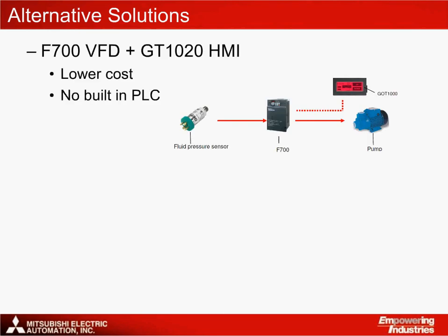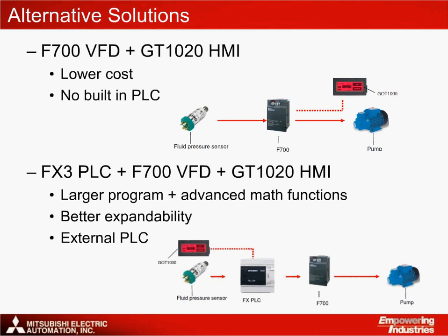As with all our applications, there are different ways to design the system solution. The F700 and GT1020 HMI offer a more affordable solution. The F700 is cheaper than the A700; however, it does not feature a built-in PLC, so while reducing cost, some functionality such as fault diagnostics within the application will be removed. Note that the GT1000 range of HMIs can connect directly to the entire range of Mitsubishi VFDs. The FX3 PLC, F700, and GT1020 solution offers different advantages to the A700 solution. The FX3 series PLC connects to the F700 via the FREQROL protocol so that it can read and write to all parameters of the drive. The FX3 offers larger programming of up to 64,000 steps for greater program size and flexibility, and there are also many more options to expand physically for more sophisticated applications.